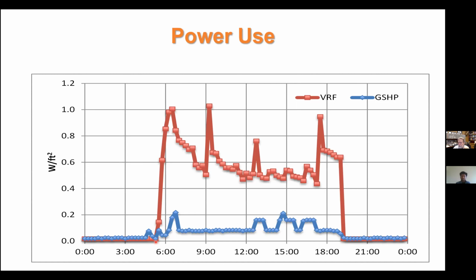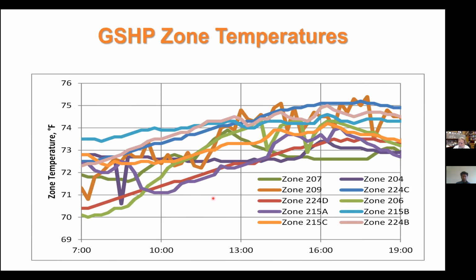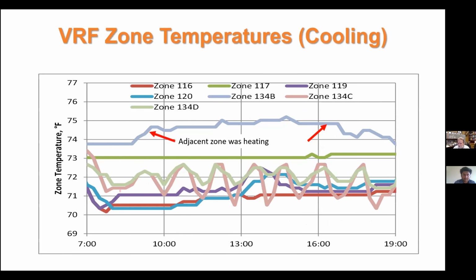Whereas the VRF system goes from near 0 to quite high all of a sudden, and that's because the VRF system during the day has all the units running all the time for the most part. It's not exactly true that they're always running, but you could say almost all the units are running almost all of the time. So in the ground source heat pump, the zone temperatures are here. You see in the morning it was cool-ish, and the deadband control between heating and cooling let the temperature sort of float up over time. Whereas in the VRF system, the units that were in cooling are here. There's 6, I think. Their temperatures fluctuate some, but they're relatively constant over the day.